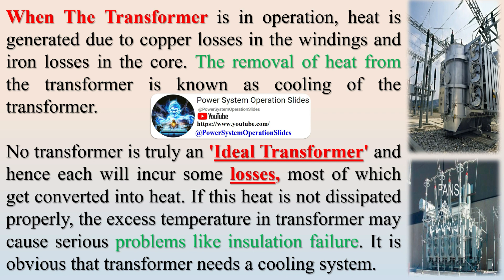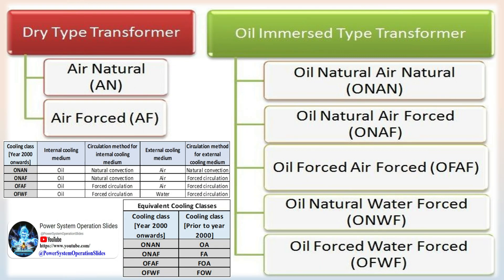Transformers are classified into two groups according to the method of cooling: dry type and oil immersed. When the transformer is in operation, heat is generated due to copper losses in the windings and iron losses in the core. The removal of heat from the transformer is known as cooling. No transformer is truly ideal and hence each will incur some losses, most of which get converted into heat. If this heat is not dissipated properly, the excess temperature may cause serious problems like insulation failure. It is obvious that a transformer needs a cooling system.